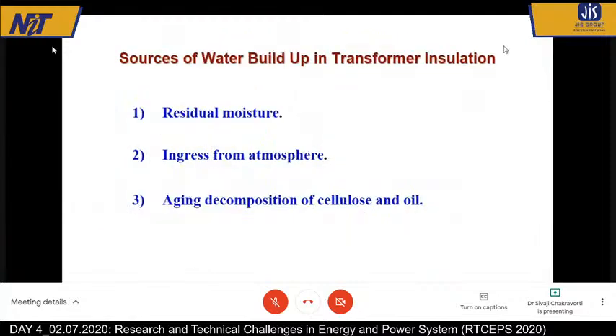Then, how does the moisture build up? One is the residual moisture. When the transformer was manufactured, we take extreme care, but still, in spite of all the heating processes, you cannot make the moisture in the insulation zero. Typically, at the time of installation of a high voltage transformer, the moisture content should be less than 5 ppm.